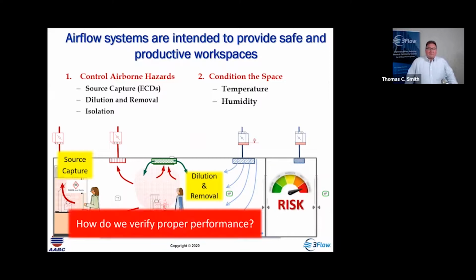So fume hoods and laboratories are designed to control exposure to airborne hazards and simultaneously condition the space. And so we want to rely on the hoods to provide source capture, and where necessary, we rely on the lab for secondary containment. And so we need to then also rely on the appropriate amount of dilution and contaminant removal. So the supply and the exhaust work in tandem to make sure that we're providing proper safety as well as appropriate conditioning of the space. So we need to then look at how do we verify that it's going to operate properly and perform to meet these objectives over the whole range of operating modes, which might be sash closed, full cooling, full heating, occupied, unoccupied operation. As these systems get more complex, the range of operating modes can vary.